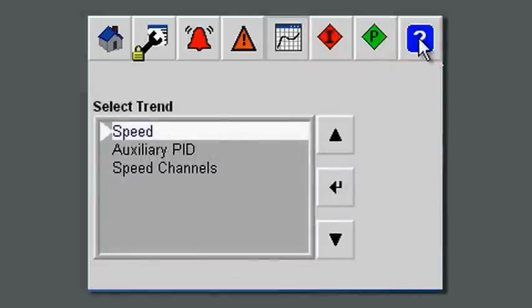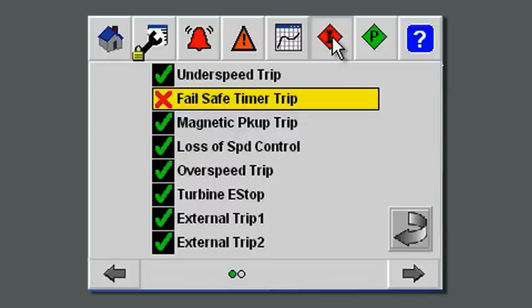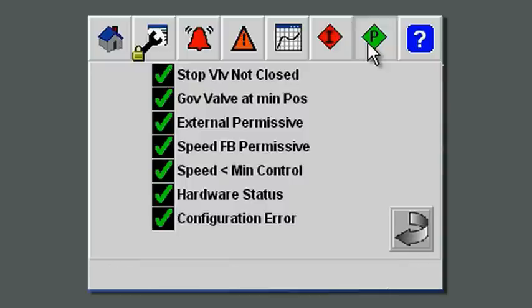The interlock page will show you the current interlocks — the ones that may be preventing you from starting. This is an interlock from a previous trip, and the turbine cannot be started until that is cleared by acknowledging and resetting the previous alarm. Permissives are on the permissives page, and these permissives have to be met before you can institute a start to bring the turbine up to speed. If you don't use these, you don't configure them. We also have online help available on the screen.